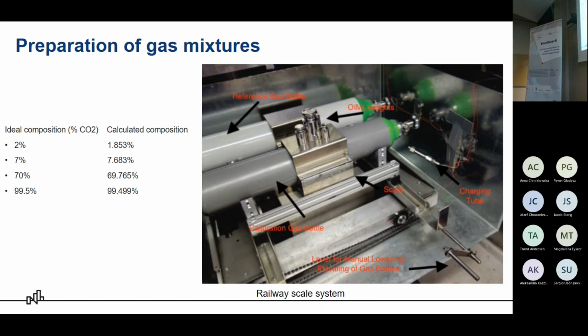We also use the OIML weights to compare the difference in mass, because firstly we inject the water, we add the water into the calibration gas bottle. We measure the mass of the water that we added. We compare it to the reference gas bottle, and the difference between the calibration gas bottle and the reference gas bottle should be as small as possible. So if we added water to the calibration gas bottle, you should also add some mass to the reference gas bottle. So for this case, we use the weights.